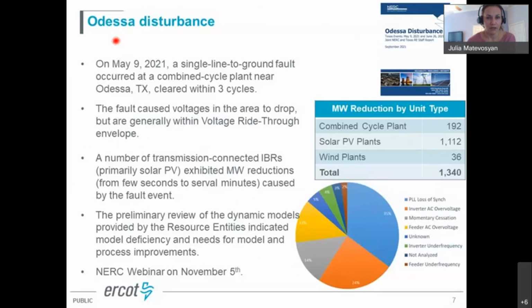You may have seen in the report that came out from NERC with an evaluation of this event. What happened in May 2021: a single line to ground fault at a combined cycle plant near Odessa, Texas was cleared normally within 3 cycles. The fault caused voltage in the area to drop, but generally it was within the voltage ride-through envelope, and voltage recovered very quickly after the event. However, a number of transmission-connected inverter-based resources, primarily solar PV, exhibited reductions in megawatt output, which lasted from a few seconds to several minutes, and that was caused by a fault event.